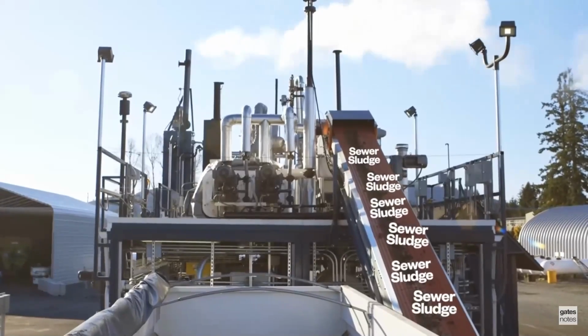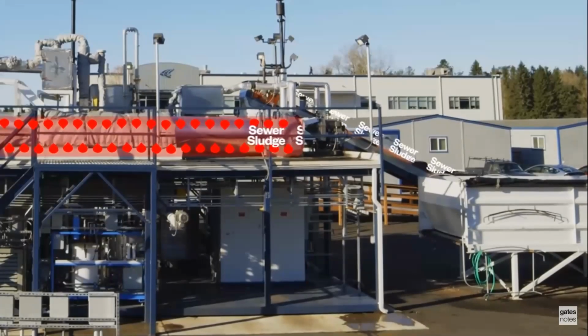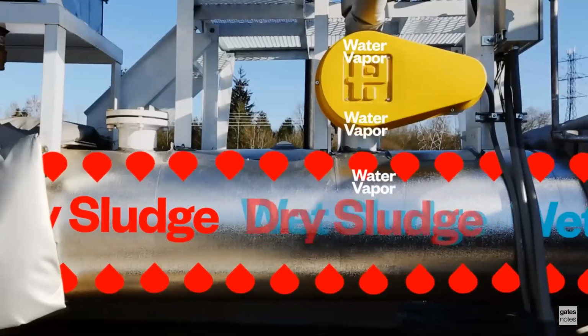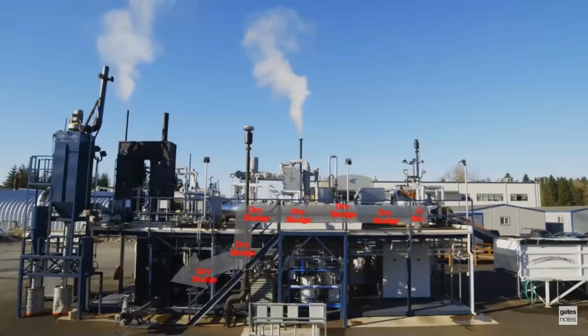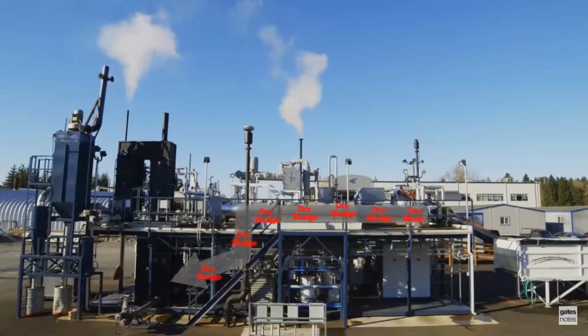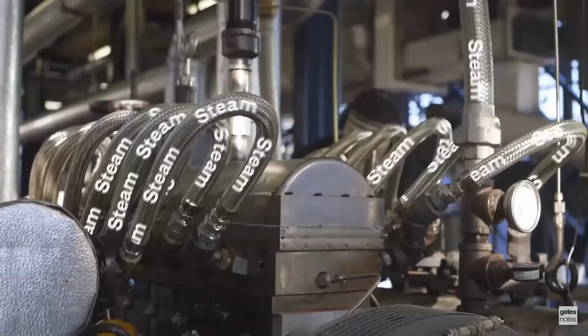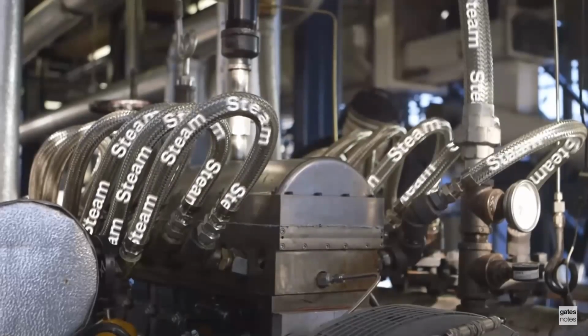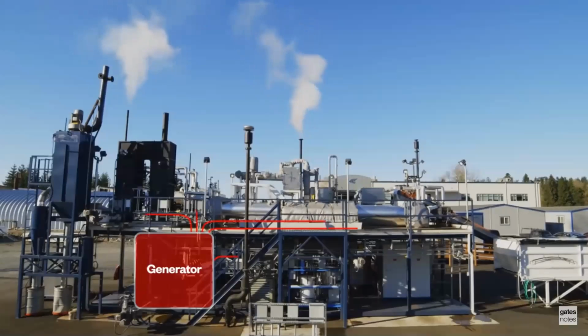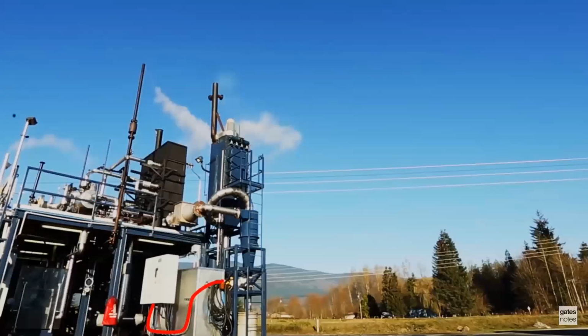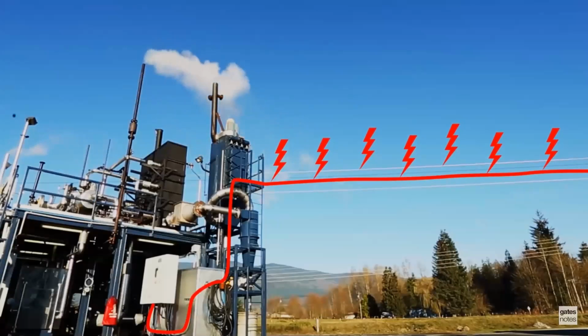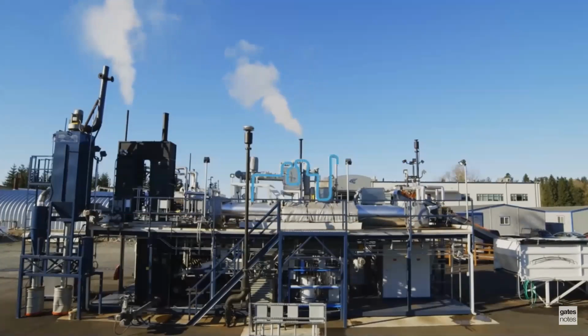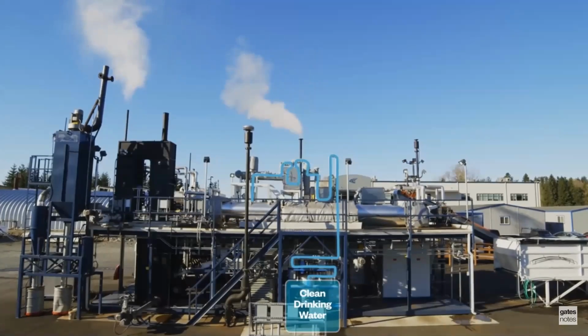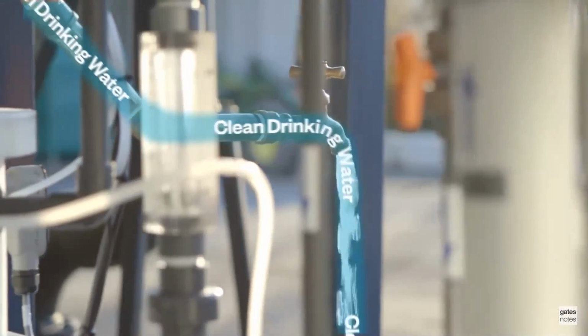It goes up this conveyor belt, is fed into these large tubes we call the dryer. That's where we boil the sludge. And in the boiling process, we separate the water vapor from the solids. The solids are now dry, and we can feed them into the fire. Once we have this very hot fire, we can make high pressure, high temperature steam. And we take that steam and we send it to a steam engine. And the steam engine drives a generator that makes electricity that we use for the processor, and also excess electricity that can be delivered back to the community. The water vapor that's created in the boiling process is run through a cleaning system until we have the cleanest, purest water you can possibly imagine.